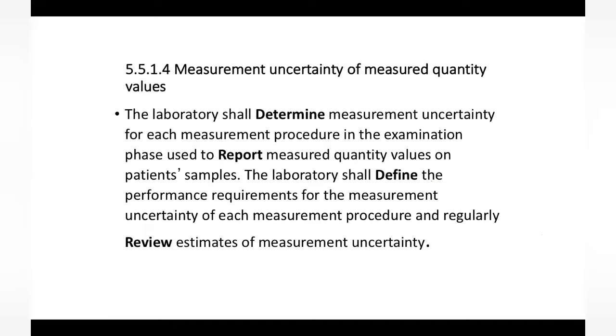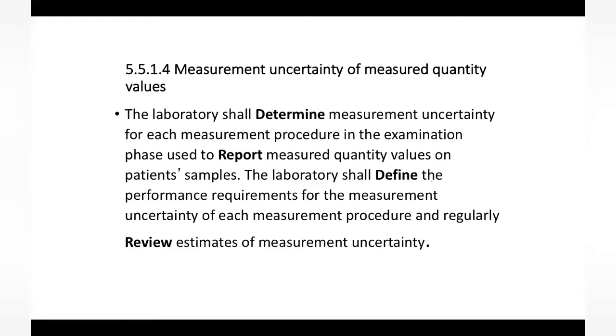Now the only certainty about measurement uncertainty is that ISO has made it a commandment. That means now it is essential. Whenever they use this word shall, it means it is a must. Laboratory shall determine measurement uncertainty for each measurement procedure in the examination phase used to report measured quantity values on patient samples. Laboratory shall define the performance requirement for the measurement uncertainty of each measurement procedure and regularly review estimates of measurement uncertainty. If you are reviewing regularly, then you will come to know how much variation there is in each parameter, whether it is increasing, decreasing, or stationary.